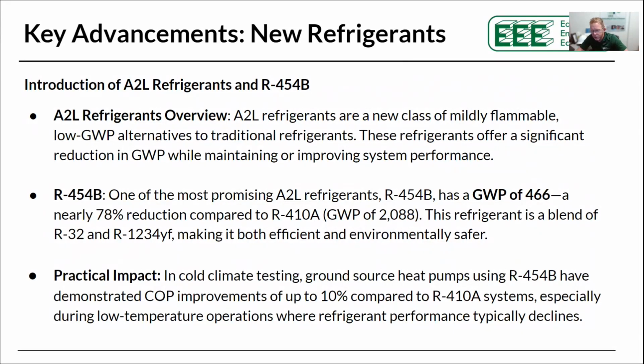The big advantage in these new refrigerants comes back to the environmental factor. We want to make sure we have a refrigerant that's good for the environment, so it has to be environmentally safe, but it also has to be efficient. When you look at 454B in comparison to other refrigerants, it has a very low GWP, which is quite helpful. The other thing about 454B is it's mildly flammable, is how it gets put to me.